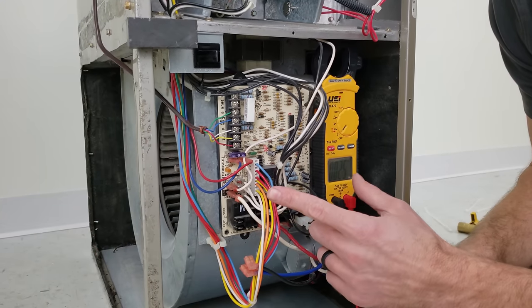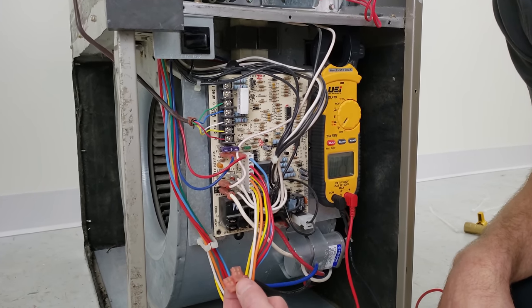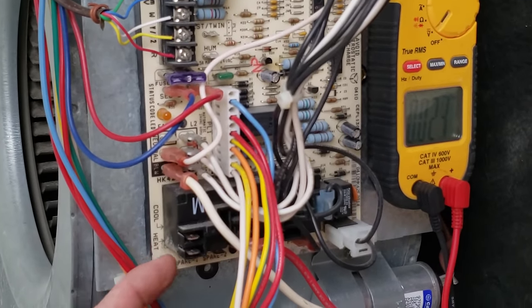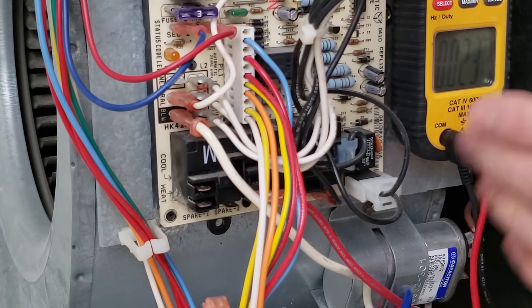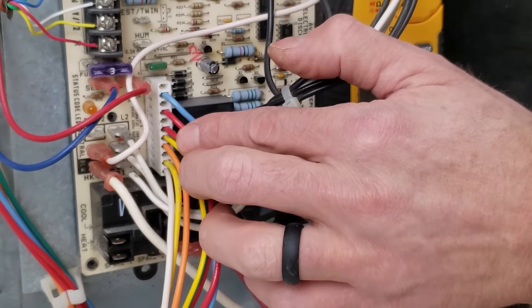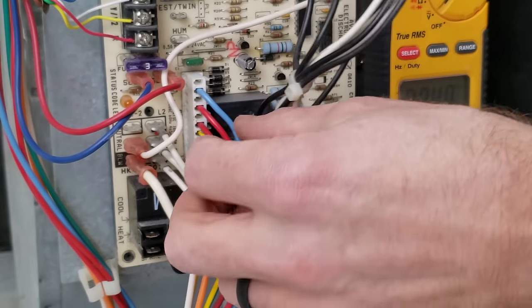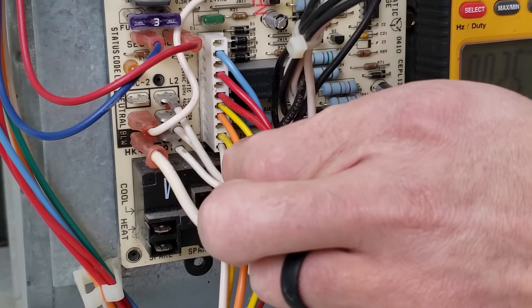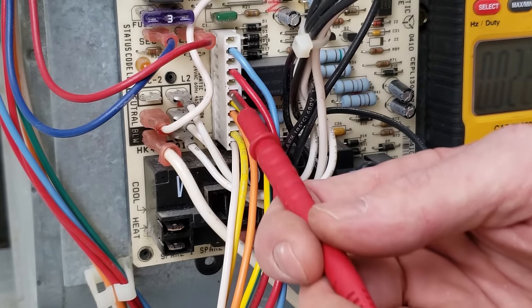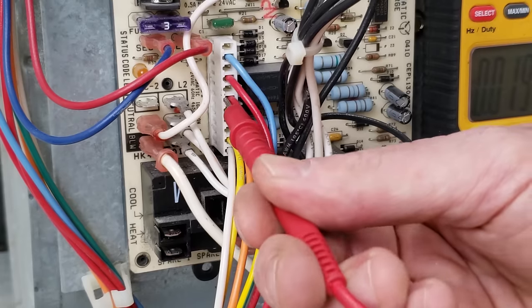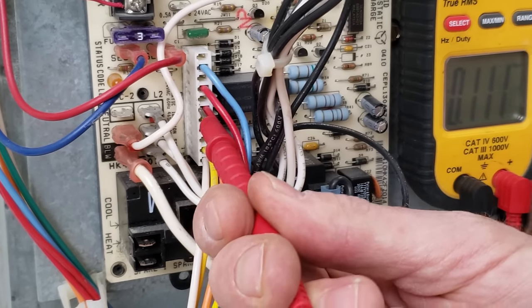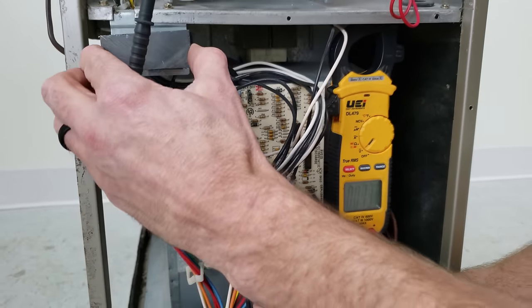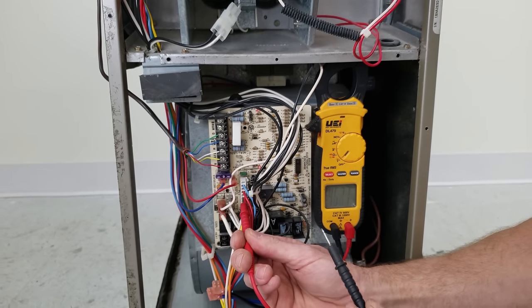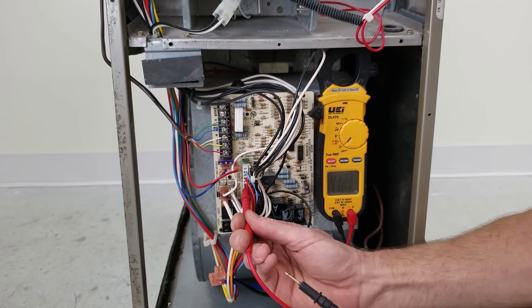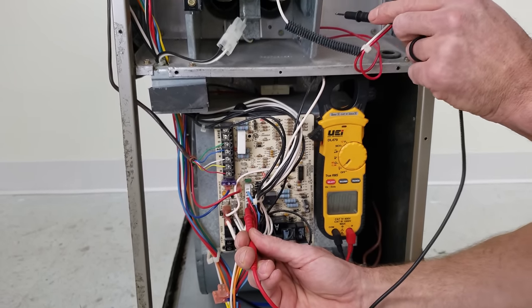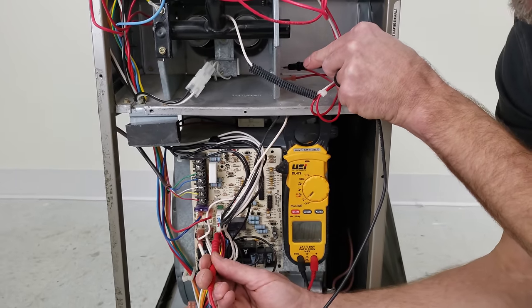So what I've done is I've turned the power off to the furnace, I've disconnected our blower motor taps from the cool and heat terminals right here. And what I'm gonna do is test for the safety switches. So you see these two wires right here. These are the two red safety switch wires. And so I'm gonna put one probe in right here, which would be, I believe, the common. And then I'm gonna turn the power on to the furnace. What I'm doing right now is just making sure that the blower motor doesn't turn on, even though there is an error. And so I'm gonna put my first tab right here.